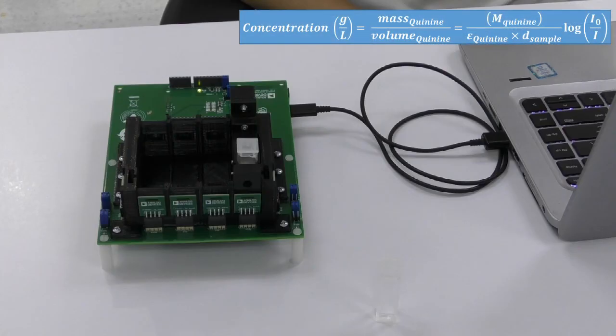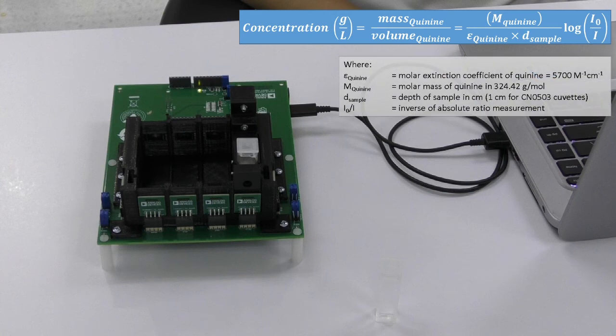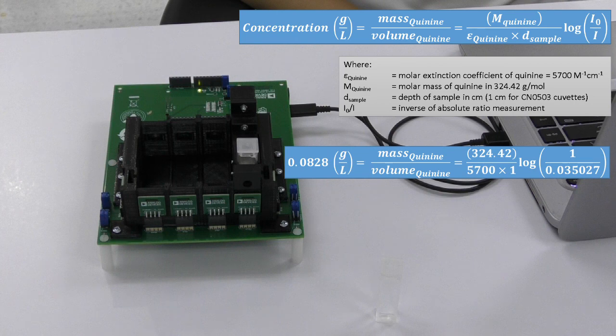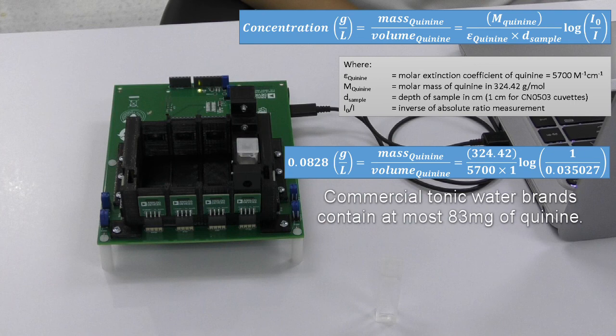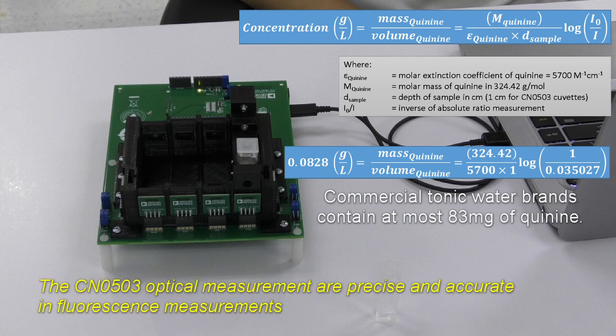We can use the inverse of this ratio in a rearranged Beer-Lambert equation to get the concentration of quinine in grams per liter. To do this, we'll need the molar extinction coefficient of quinine, the molar mass of quinine, and the depth of the sample in centimeters, which is, in our case, 1 centimeter. If you factor all these into the equation, we'll get the concentration of quinine as 82.8 milligrams per liter. Commercially available tonic water brands have at most 83 milligrams of quinine in every 1 liter bottle. This means that CN0503 measurements are not just precise, but are also highly accurate.